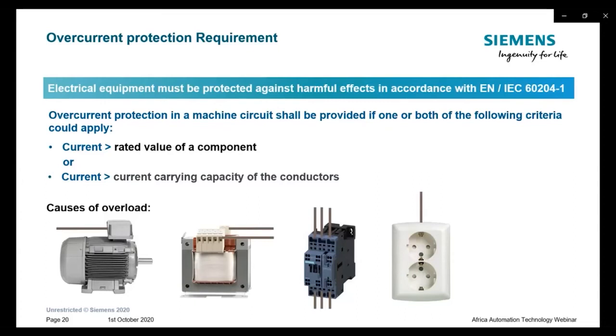Overcurrent or short circuit current is, besides harmful temperature, one of the most important aspects of risk in electrical equipment. Overcurrent protection includes the short circuit protection of the equipment. As a result, all electrical components used with the electrical system need to be considered on their current carrying capacity. This is independent from the component itself or the electrical connection by conductor or cable.